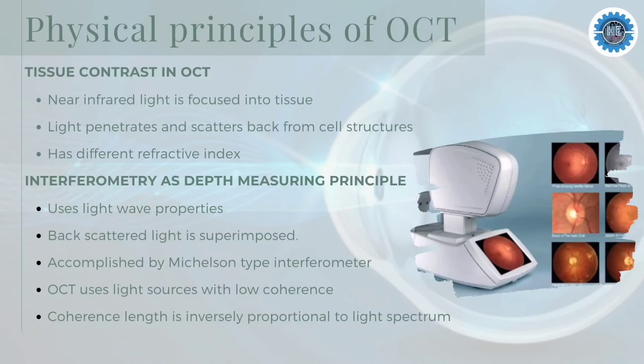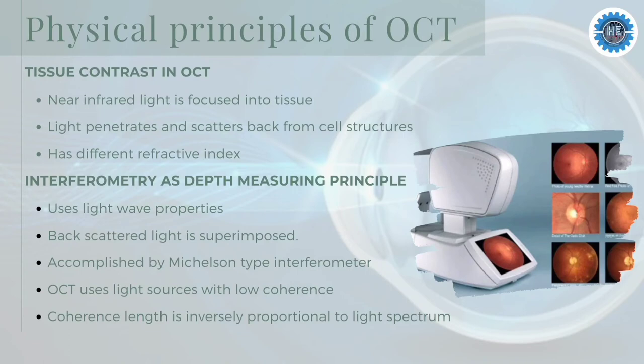The first physical principle of OCT is Tissue Contrast. Optical Coherence Tomography displays cross-sectional images of biological tissue. A near-infrared light is moderately focused into the tissue structures, where it penetrates and scatters back from cell structures like nuclei, mitochondria, membranes, or collagen fibrils. These structures have a different index of refraction than the surrounding layer, forming inhomogeneities in the refractive index of the tissue, which gives rise to scattering. The back-scattered light is then analyzed in the OCT system.